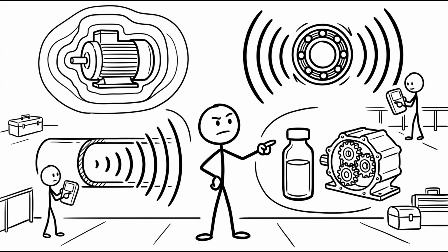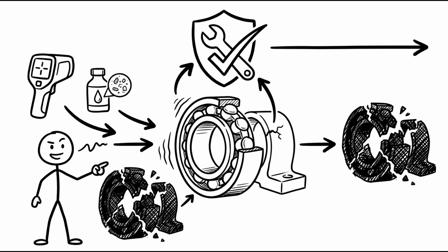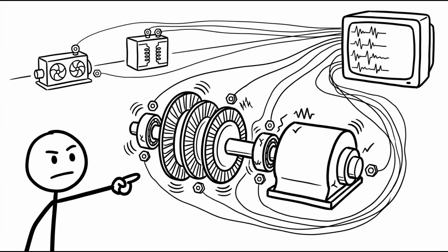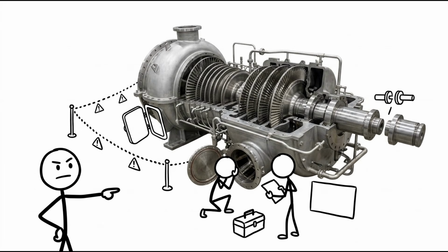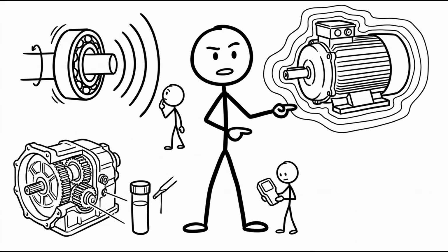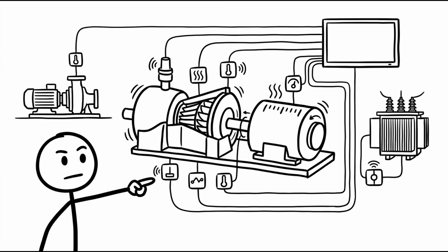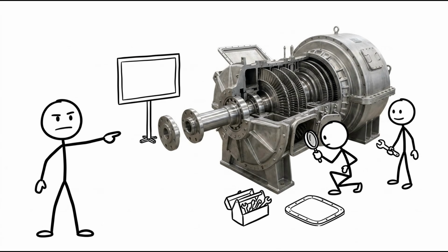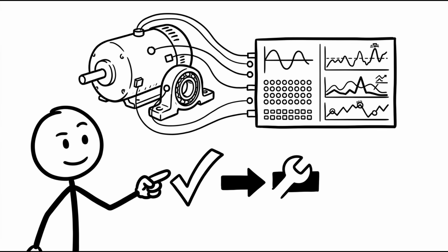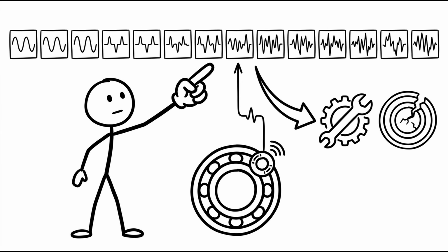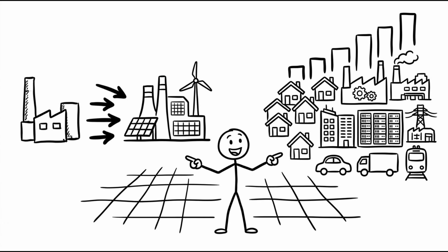Maintenance is another enormous operation. A power plant may contain thousands of pumps, valves, motors, turbines, transformers, sensors, and miles of piping. Engineers use vibration analysis, thermal imaging, oil testing, ultrasonic inspections, and other techniques to detect problems before they cause failures. Some equipment is monitored continuously, while major components such as turbine systems may be inspected during scheduled outages. Predictive maintenance software can analyze equipment data and identify patterns that indicate a component may need service before it breaks unexpectedly.